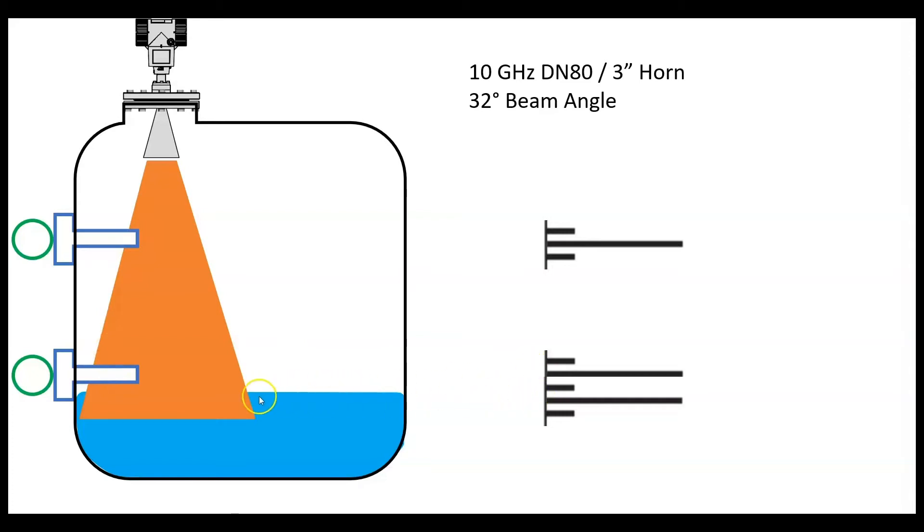What you as a user could do is tell the radar, ignore this, that's not the level, that's a thermowell, and ignore this, that's a thermowell, that's not the level. And the radar goes on and says, okay, I'm going to ignore these two signals reflections I get from these, and you go on your way.